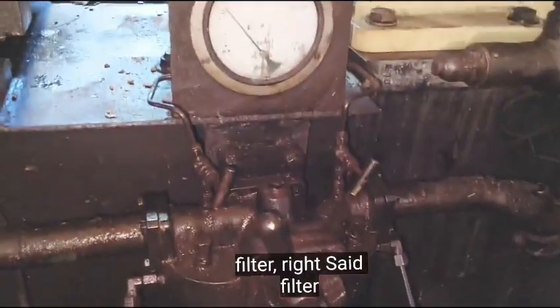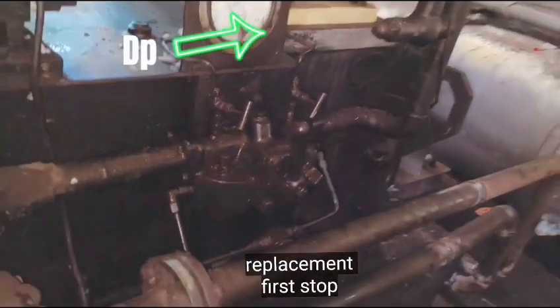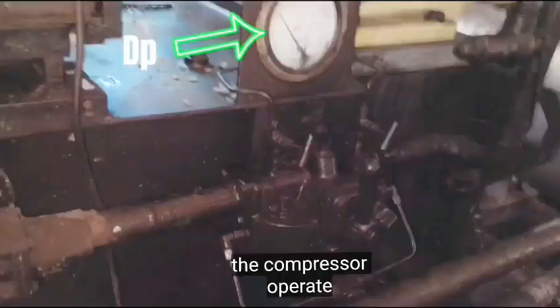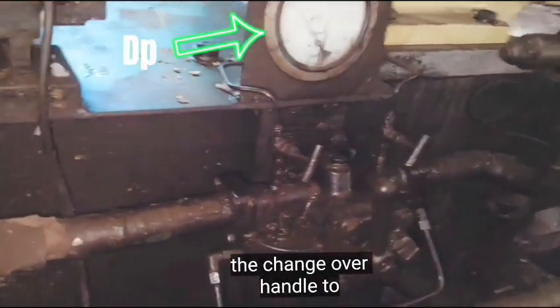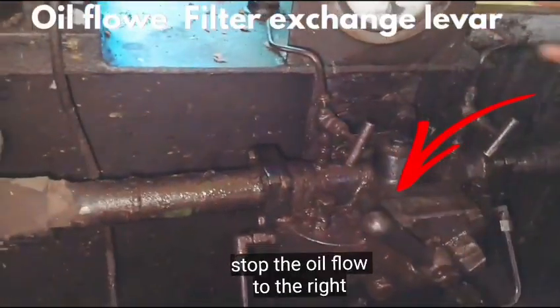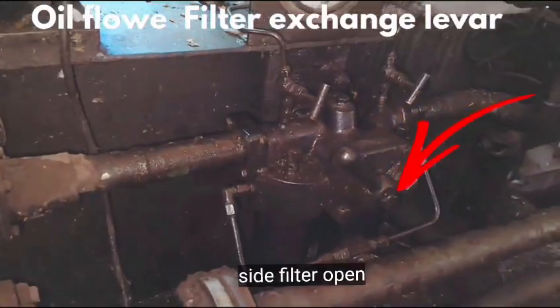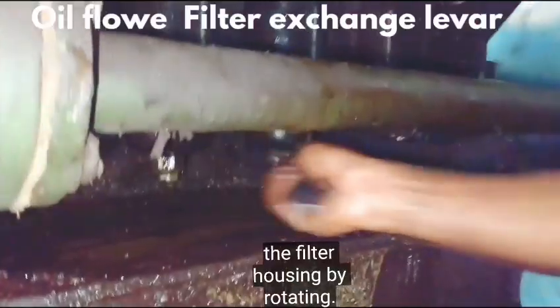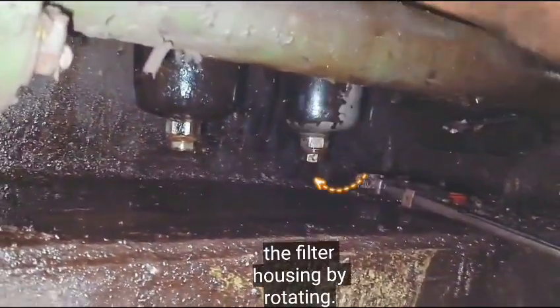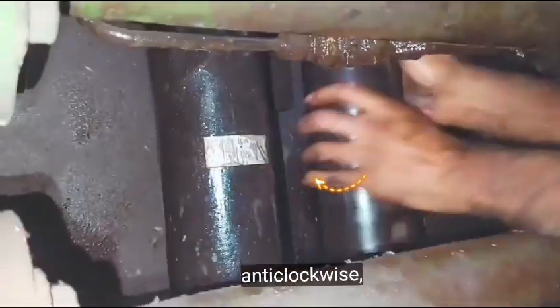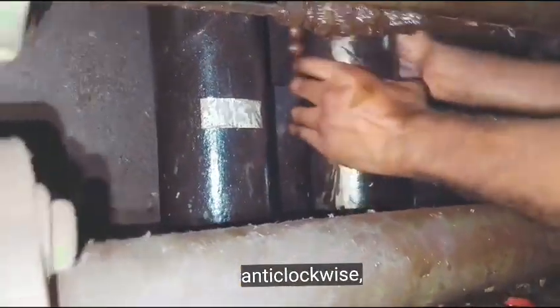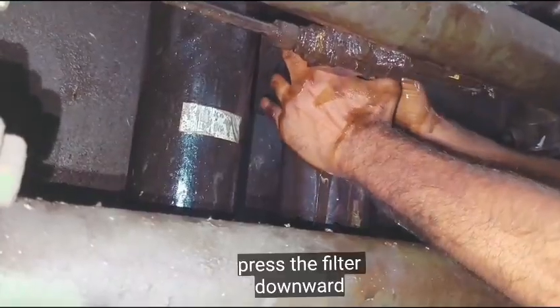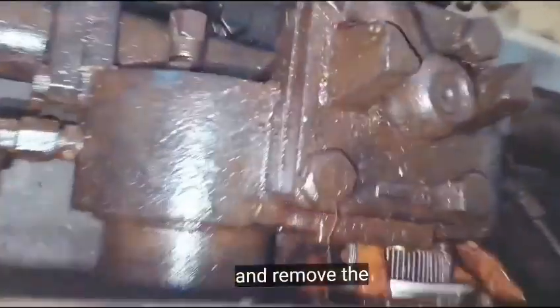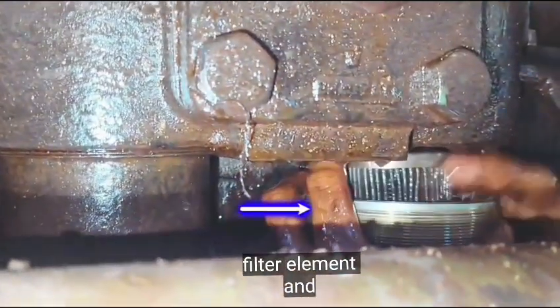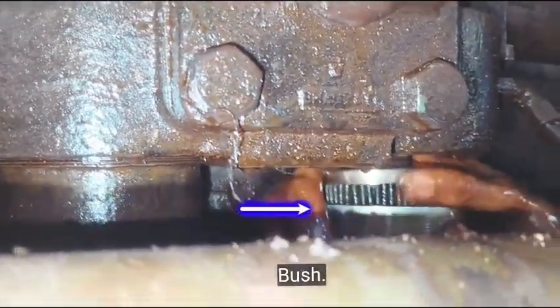Right side filter replacement. First stop the compressor. Operate the changeover handle to stop the oil flow to the right side filter. Open the filter housing by rotating the bottom nut anti-clockwise. Press the filter downward and remove the filter element and nylon bush.